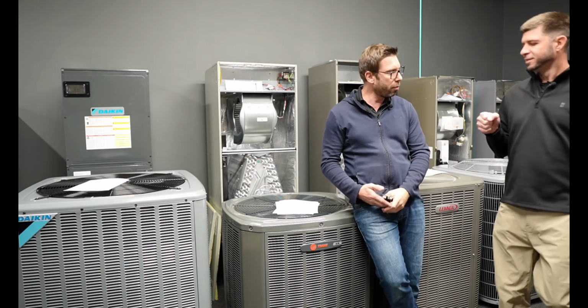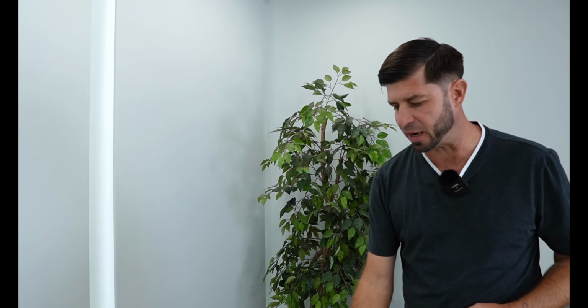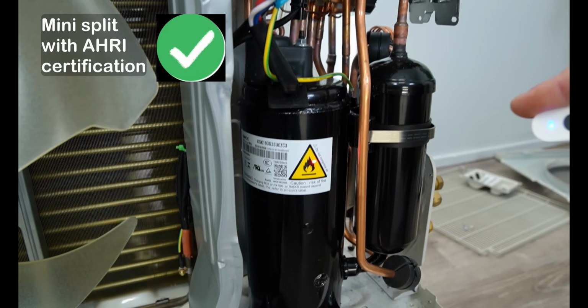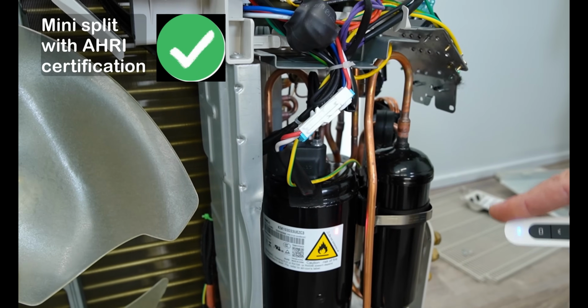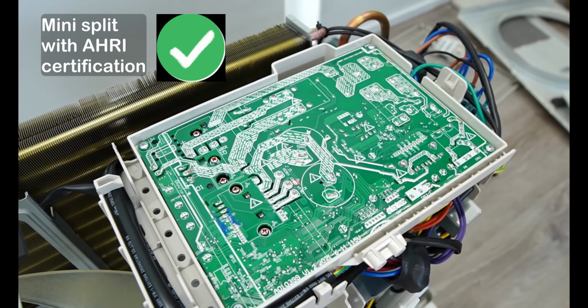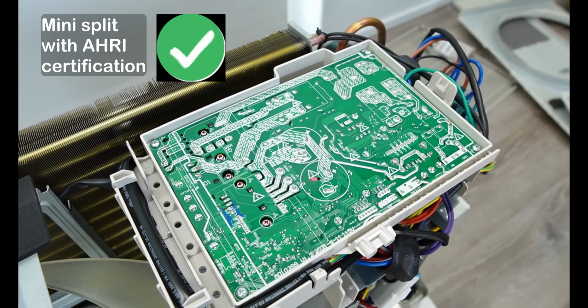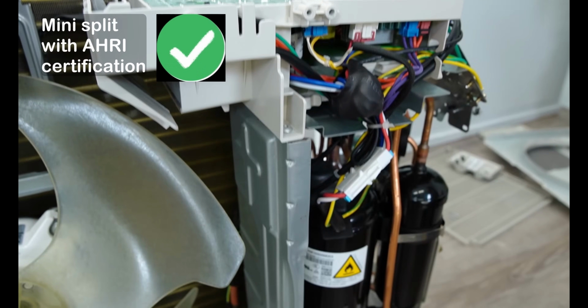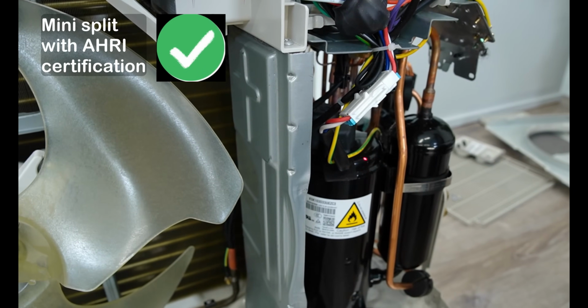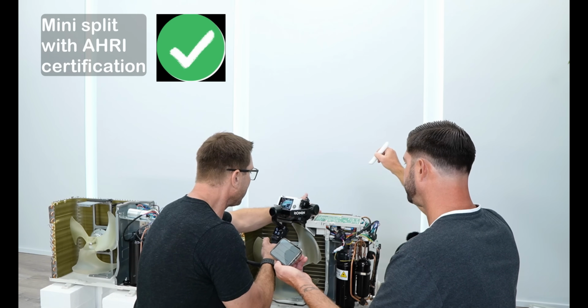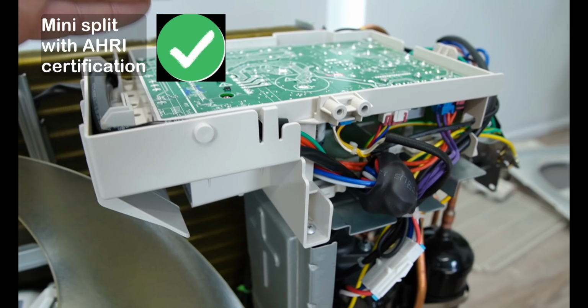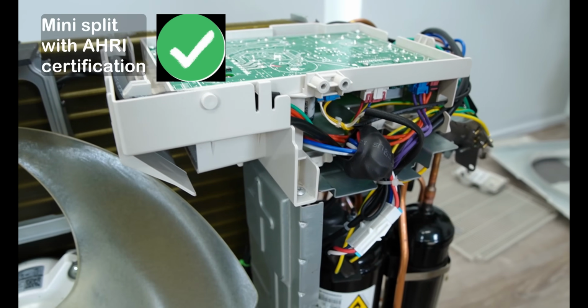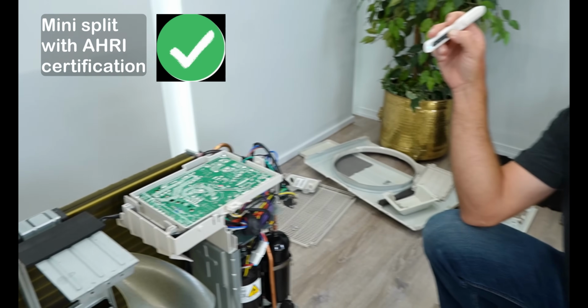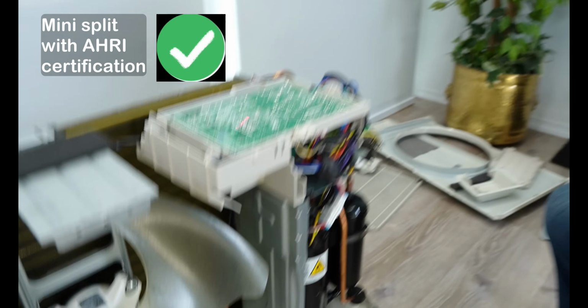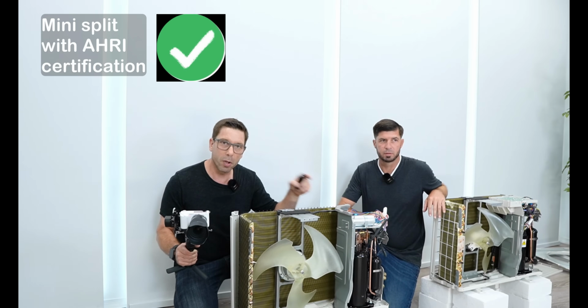When it comes to higher efficiency, that can only be achieved with a variable speed compressor like this one here. So this is a variable speed compressor that runs on DC voltage. This inverter board changes the AC voltage to DC voltage, allowing the compressor to speed up and slow down as needed. Without an inverter board like this, you can't achieve high efficiency. It's impossible. So without this inverter board, it's basically operating as a single stage system. Now let's see what's in here.